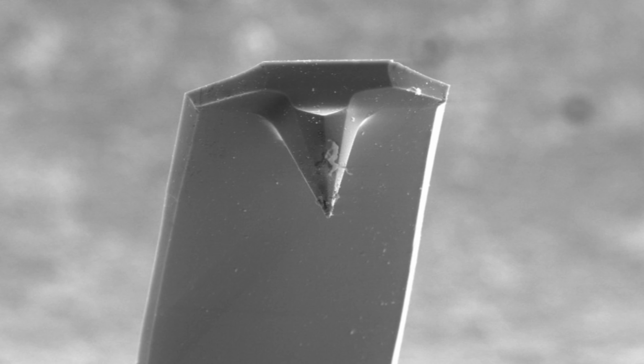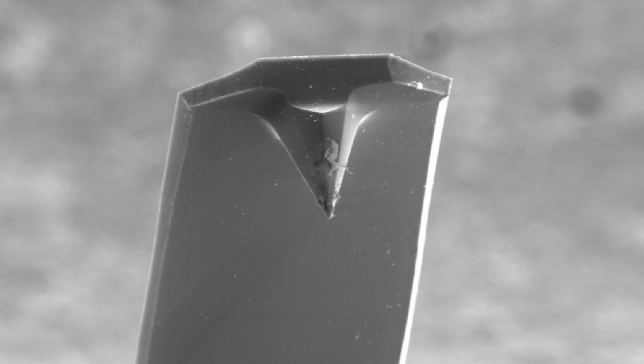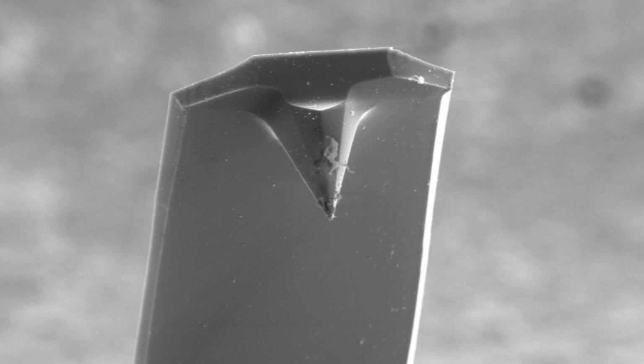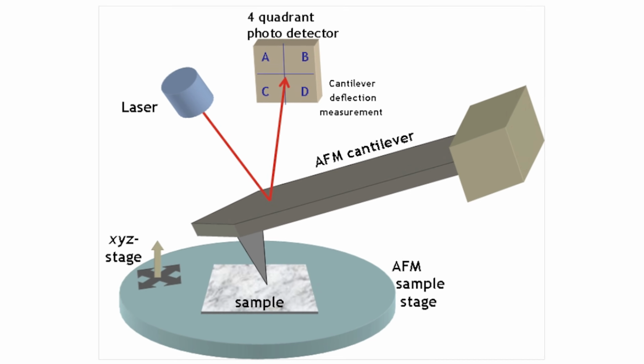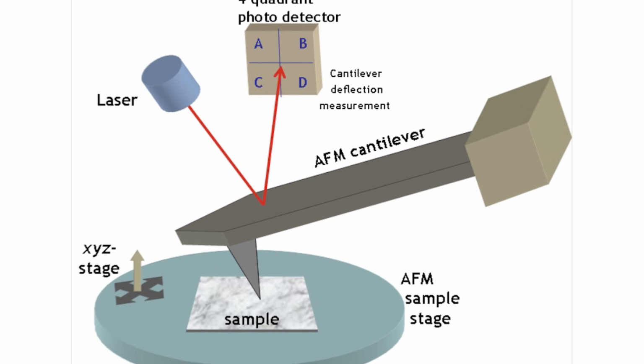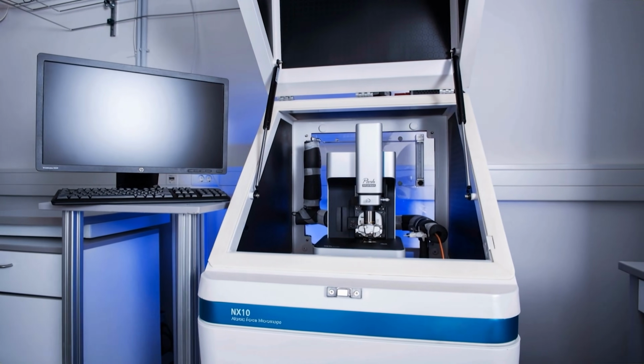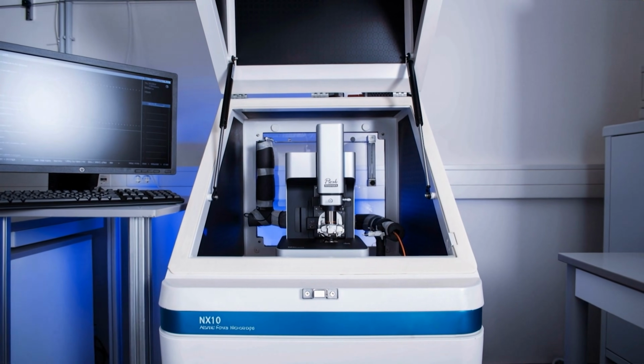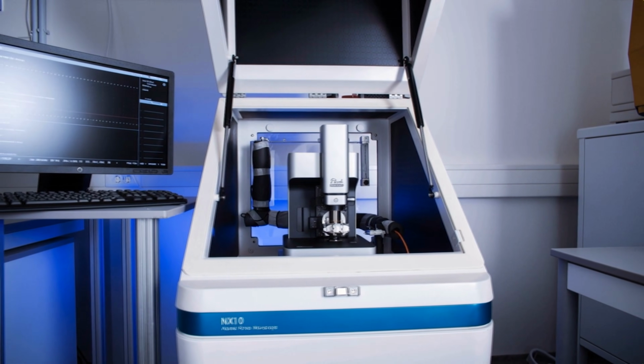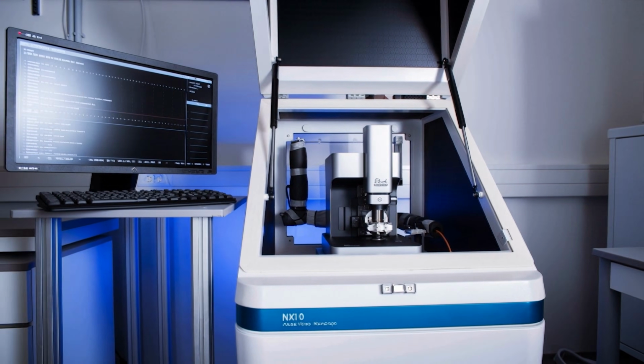This microscope works by scanning a nanoscale tip across a surface. This tip is mounted on a flexible cantilever that bends in response to forces between the tip and the atoms on the surface. These forces can be mechanical, electrostatic, or even chemical in nature. As the tip moves across the surface, a laser detects tiny deflections in the cantilever, which are then converted into a detailed image.